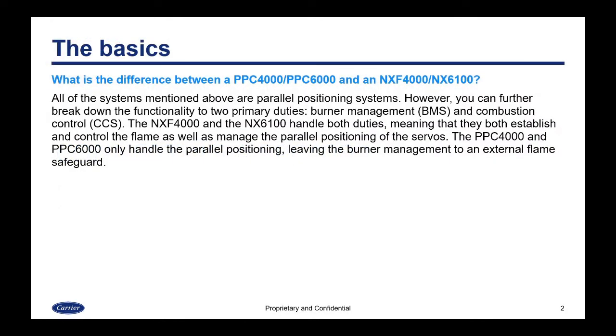So let's start with the basics. What is the difference between a PPC4000 or PPC6000 and, say, an NXF4000 or an NX6100? All of the systems mentioned above are parallel positioning systems. However, you can further break down the functionality to the two primary duties they have: burner management, or BMS, and combustion control, or CCS. The NXF4000 and the NX6100 handle both of the duties, meaning they can both establish and control the flame, such as a flame safeguard would do, as well as manage the parallel positioning of the servos. The PPC4000 and the PPC6000 only handle the parallel positioning portion, which leaves the burner management to an external flame safeguard.